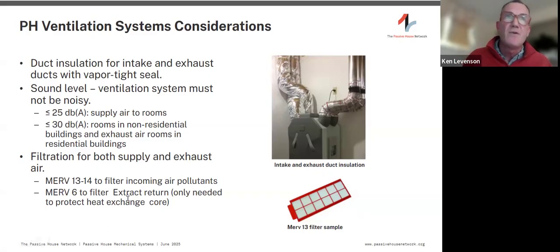And then for that quality, the filtering of the fresh air, we want it on the supply side to have MERV 13 minimum, and on the exhaust side, it could be lower, to MERV 6. We can see higher filtration, and we see in smoke areas where people have done supplemental filtration. But it does have a basic requirement of a MERV 13 air filter.